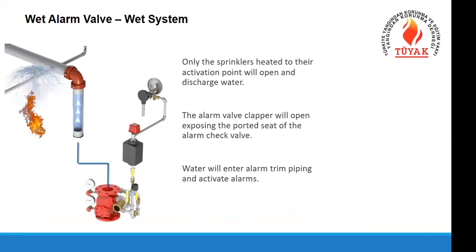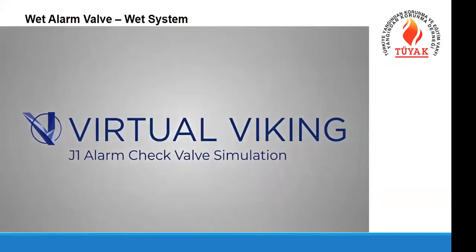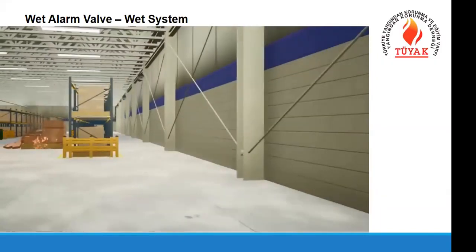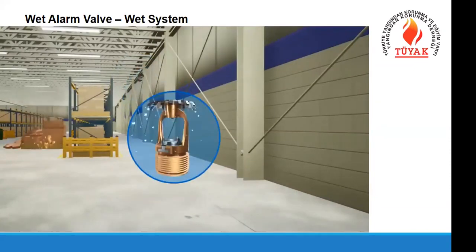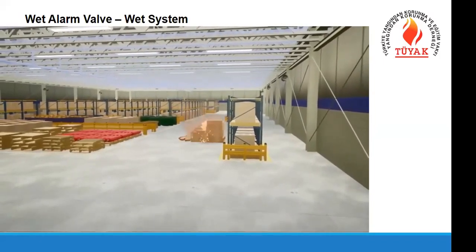The purpose of this valve is to get an alarm from the system and also to test the system before a fire happens. We want the system to inform us when a fire happens or a sprinkler operates, giving either a mechanical or electrical alarm. In the animation: a fire has started in the building. As the fire grows and the heat reaches the rated temperature, the sprinkler activates. Since this is a wet system, water is already in the pipes, allowing immediate delivery of water to the fire.